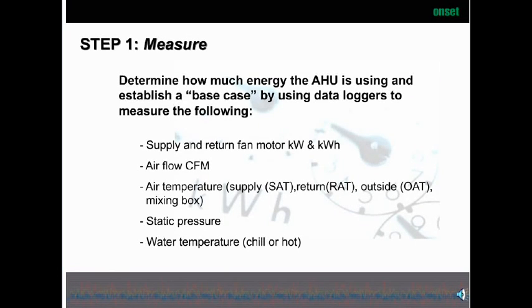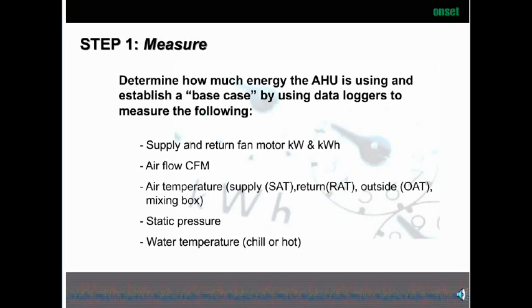In the utility and rebate world, we have to determine our base case. That means looking at your supply and return fan motor KW and KWH — how much energy it takes to move this air. Also the airflow in CFM, how many cubic feet per minute are we moving. The air temperature: supply, return, outside air temperature, and your mixing box temperature. What's the static pressure in the system? And your water temperature, whether chilled or hot, depending on whether you're in summer or winter mode.